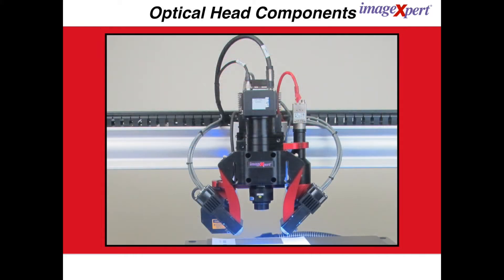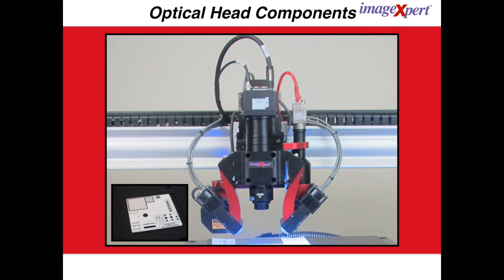All the components needed for a complete scanning system are included in the compact optical head. Two cameras are mounted side-by-side: a two-dimensional camera for barcode recognition and for finding fiducials, and a 6000 pixel line-scan camera for capturing high-resolution images of the dot pattern. Both cameras can be periodically calibrated via the embedded calibration target. The optical head also includes a laser measurement system, z-axis motion, and two light sources.